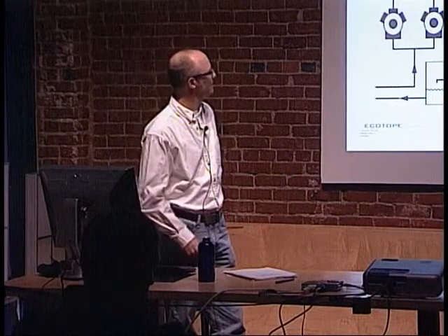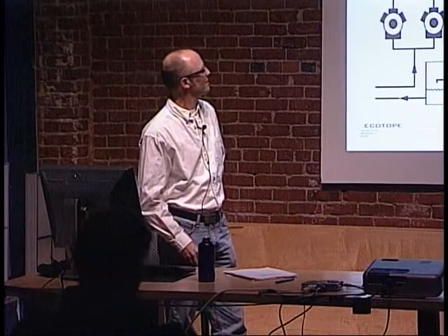Typical stores that I've been working on, the air handler is actually contained within the building at the same level as the compressor rack, as opposed to being on the roof. Do you have any problems, or is it still possible to allow that kind of condensing, and when the compressors do the work to push the remainder up to the condenser on the roof, as opposed to keeping everything up on the roof and keeping it connected and utilizing gravity as much as possible?